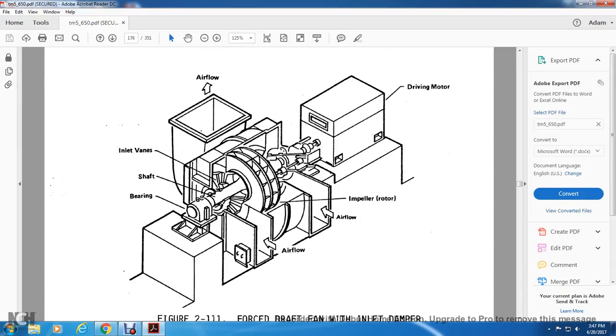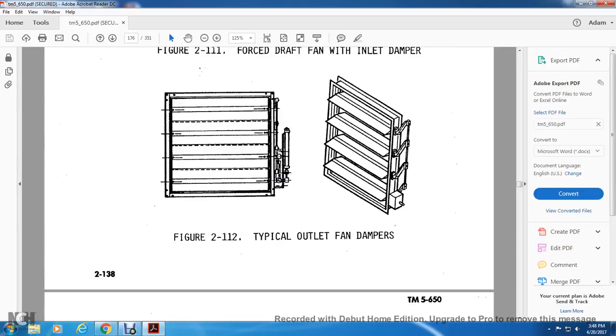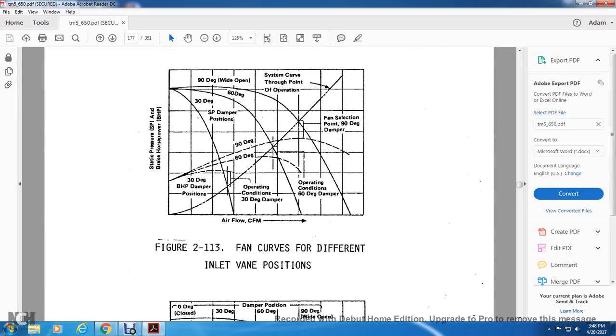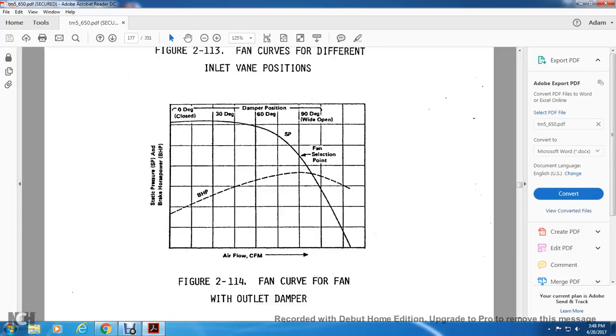Alright, this one, figure 2-111, shows a forced draft fan with an inlet damper. The airflow goes in through the impeller rotor, with the bearings and shaft on the impeller rotor, the inlet vane, and the driving motor. Figure 2-112, typical outlet fan dampers. They are bush-like shutters that hang over the ducts. Figure 2-113, fan curves for different inlet vane positions: airflow in CFM, static pressure, and brake horsepower. Figure 2-114, fan curve for a fan with an outlet damper: airflow in CFM and brake horsepower over the static pressure.